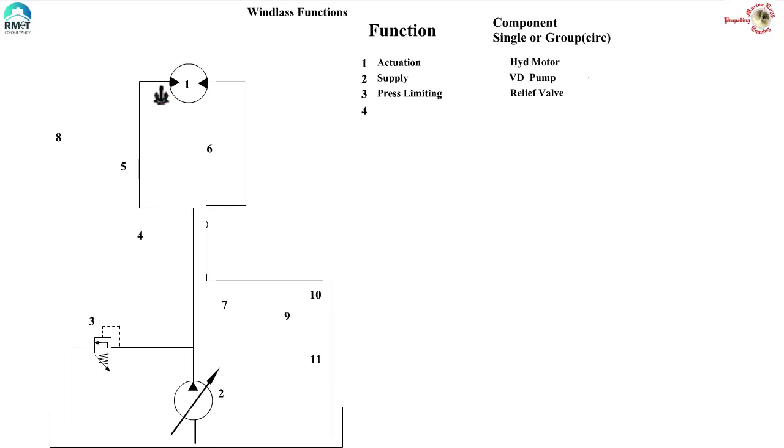Next, if I start the pump, the oil is entering the motor from left hand side and the anchor will lift up. Then, how can the anchor be lowered? I need to make the oil enter from the right hand side. The function here is reversing and the component doing the job in this circuit is direction control valve. To know more about the direction control valves, the type of valves and other details, please see my earlier video on direction control valves.